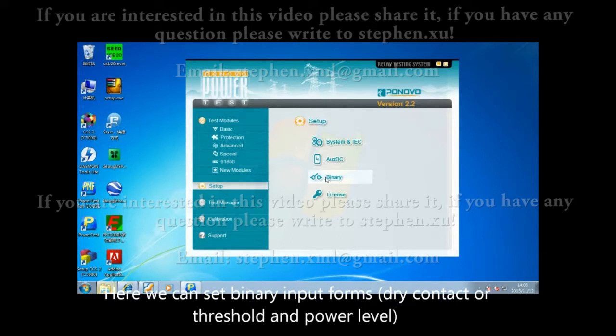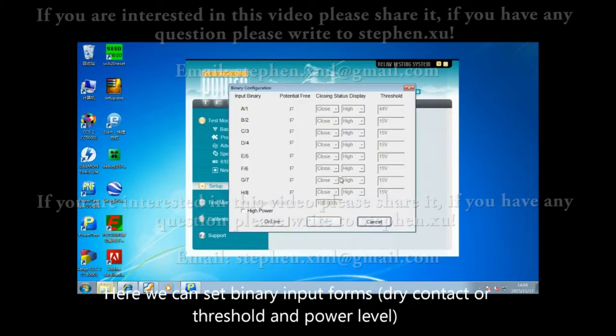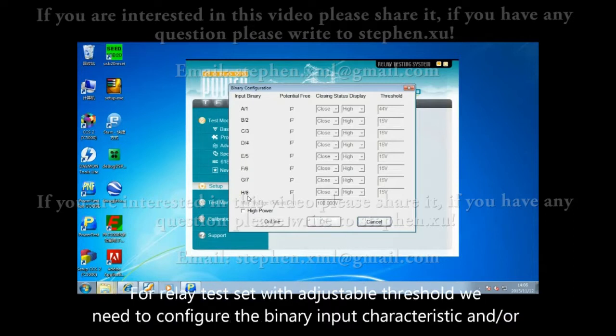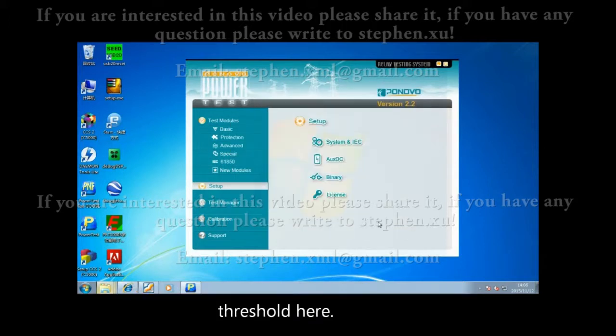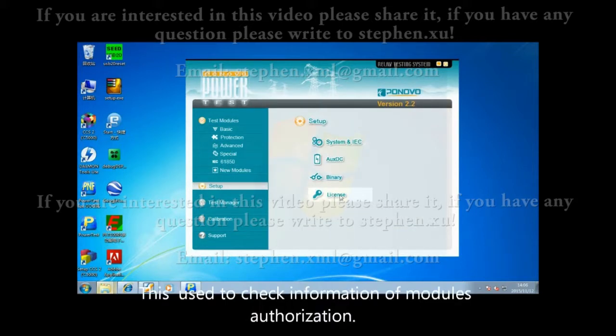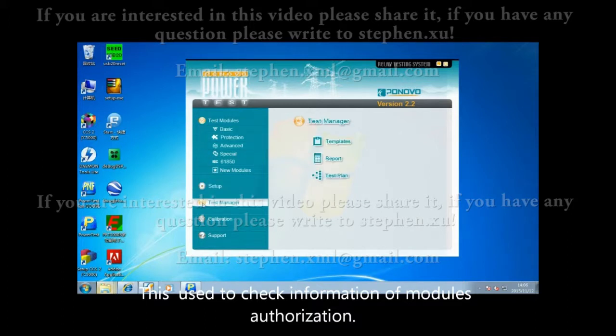Here we can set binary input forms, dry contact or threshold and power level. For relay test sets with adjustable threshold, we need to configure the binary input characteristic and threshold here. This is used to check information of modules authorization.